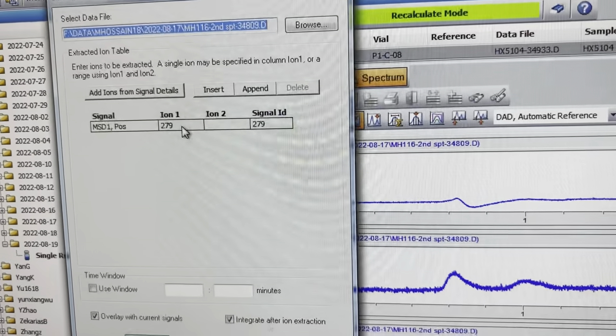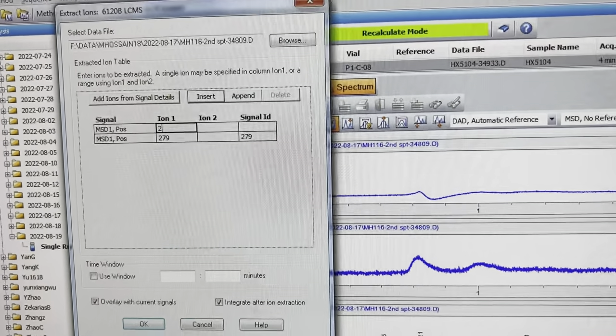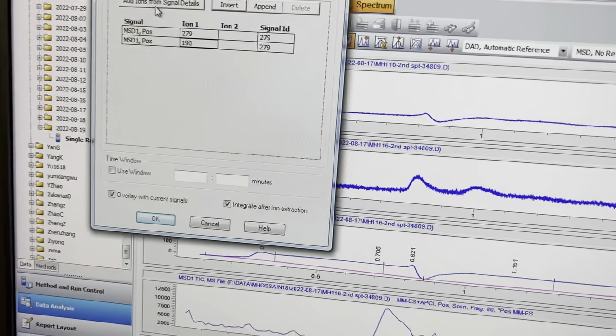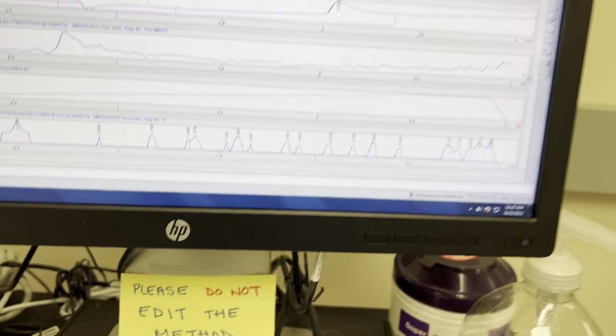Double-click the data file to open the chromatogram. The top chromatograms are UV chromatograms detected by the UV detector. Since it is connected to the LC-MS, you can click on the chromatogram to also see mass data. Before doing that, you can do 'Extract Ions' — click that and put the expected mass value you are looking for. You can insert multiple ion values if you suspect certain fragments. Click OK and it will show the chromatogram with those extracted ion peaks.